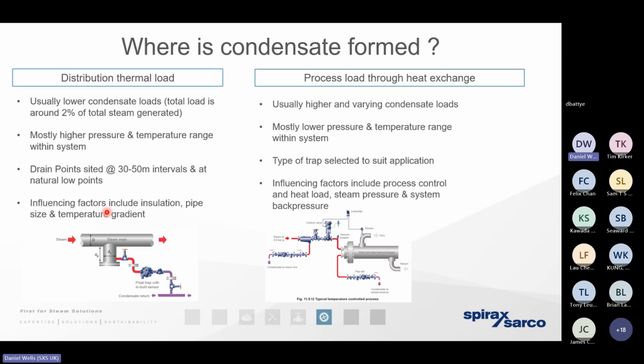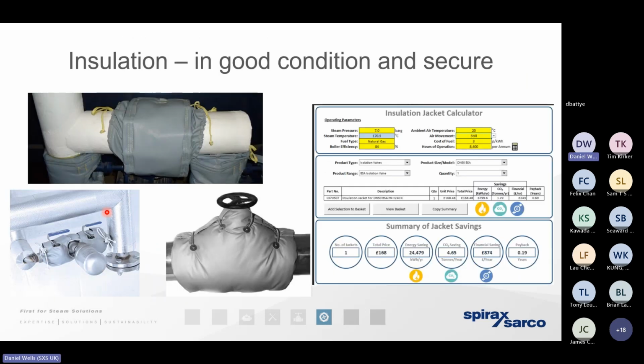So as far as the heat exchanger is concerned, we might want to apply an even bigger diversity factor. We might want to not just multiply the capacity of the trap by 2, we might want to multiply the capacity of the trap by maybe 3 times, just to guarantee that we can get that barrier to heat exchange away very, very quickly. So I've mentioned that rule of thumb, factor of ×2, maybe even ×3 at a process. But that really is a rule of thumb. And if we know for a fact that we've got excessively wet steam, if we've got undersized pipework, or if we've got poor, damaged, missing insulation, then that might be on the low side.